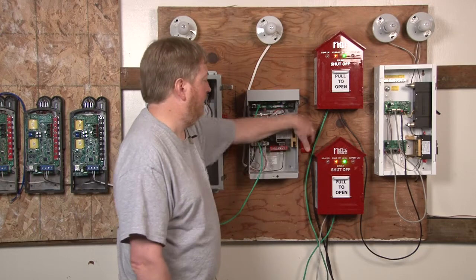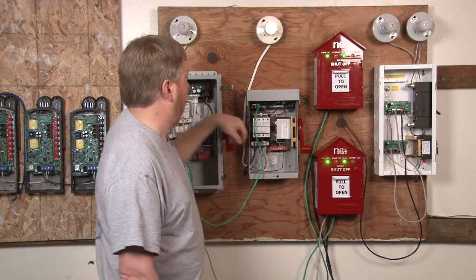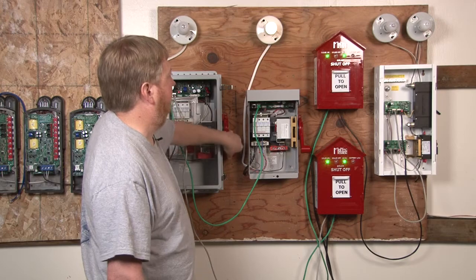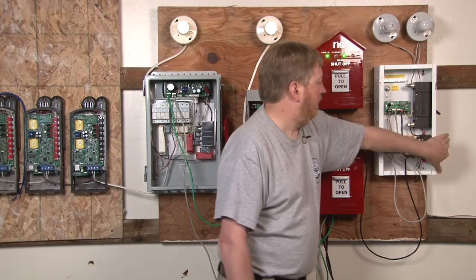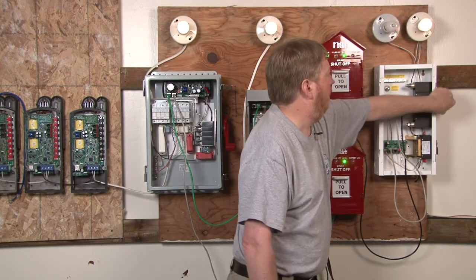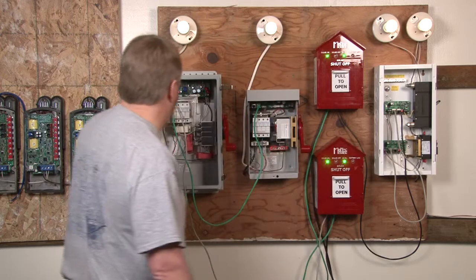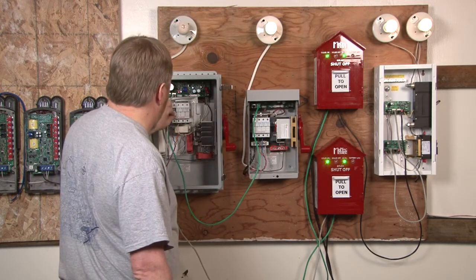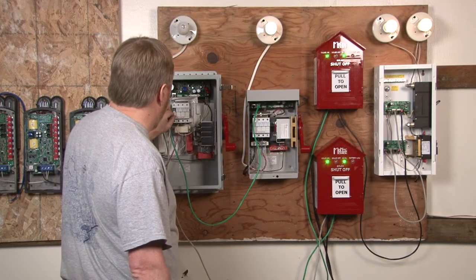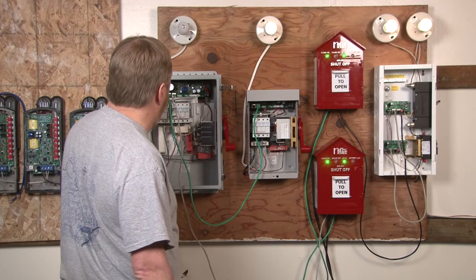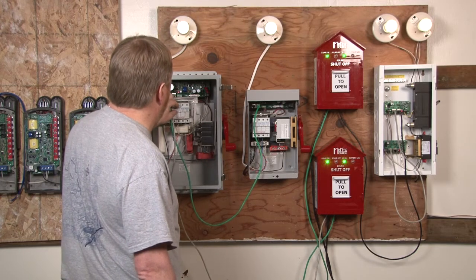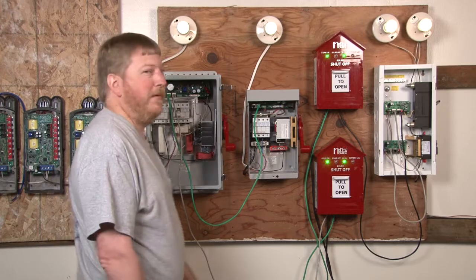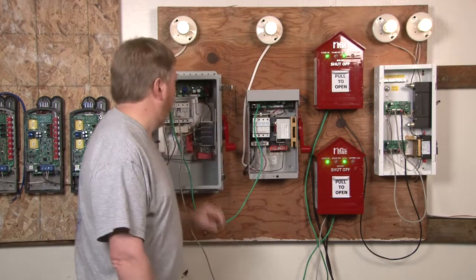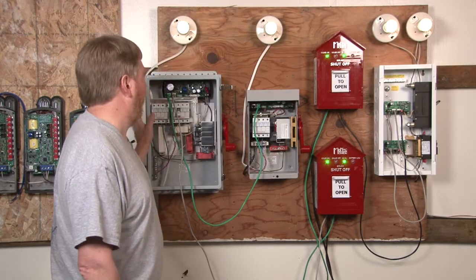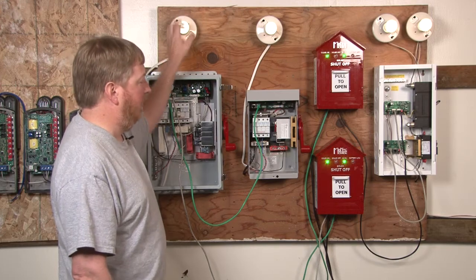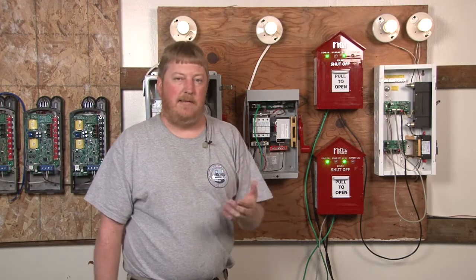Now what I'm going to do is reset the whole system. The combiner circuit breaker is closed. And I'm going to open this fuse holder here, mimicking this fuse holder. I'll get the right one, bear with me. That's mimicking PV input. So now we've turned off the PV to the combiner box, but as you can see the switch is still on. So now we're going to give you the nighttime announcement.